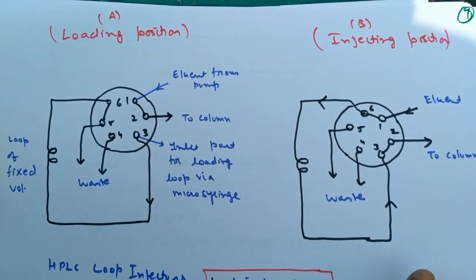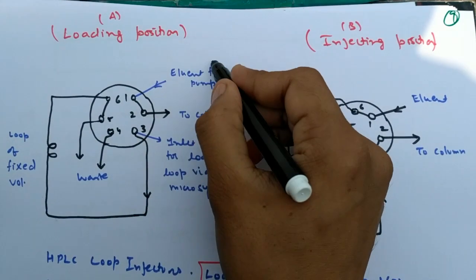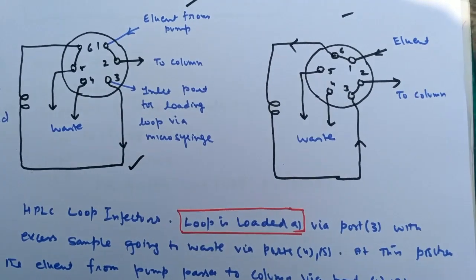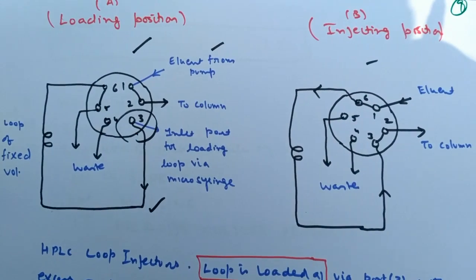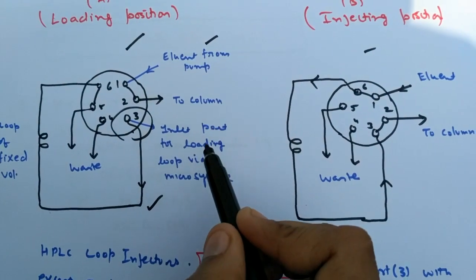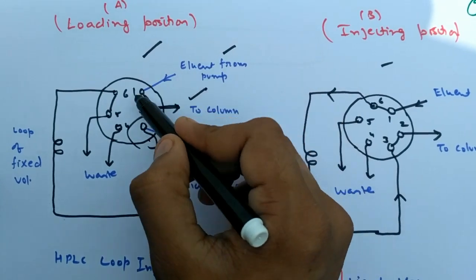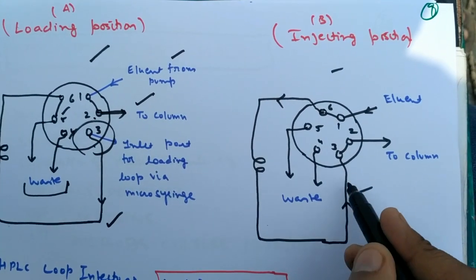The piston positions include loading position and injecting position. For the HPLC loop injector: in the loading state, the setting must be on the loading position. We inject the sample through port number 3 using a syringe. From port 1, the solvent is pumped and sent to port 2 and then to the column. Excess solvent drains into a waste container through ports 5 and 6. In the injecting position, the eluent flow goes from port 1 to 6, then 3 to 2 to the column, while ports 5 and 4 contain excess solvent as waste.